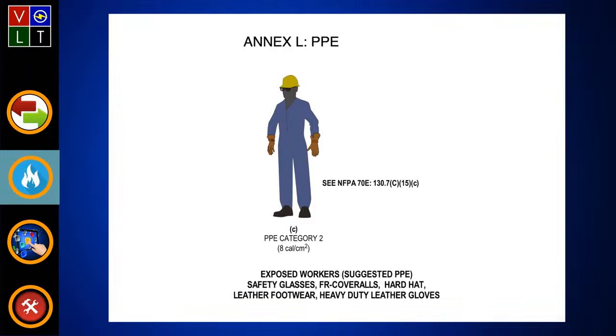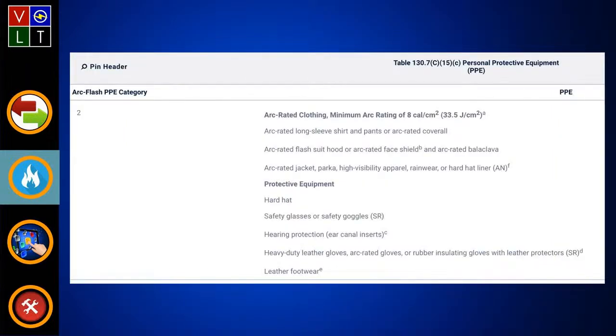So are you saying that's an 8-cal, what we're seeing there? Yeah, that's an 8-cal, and you find that in table 130.7C, 15C. This is what you would wear - there's the ARC-rated clothing for 8-cal, and the protective equipment below that you'd need to wear.